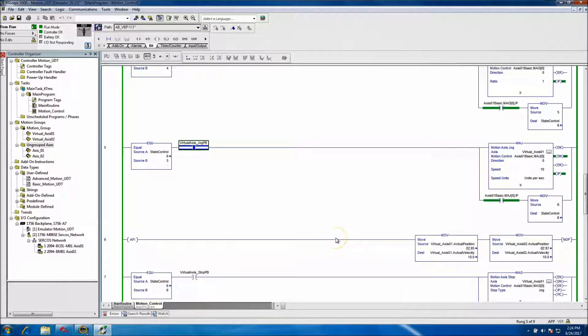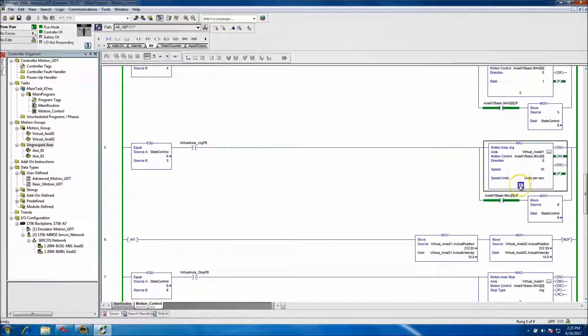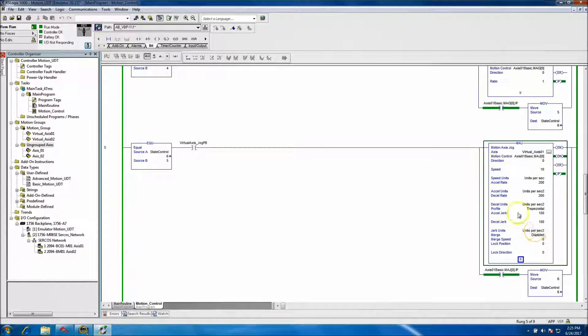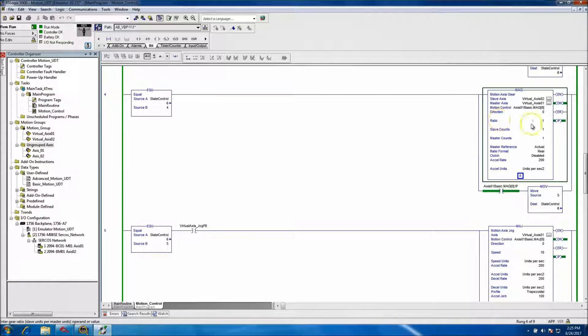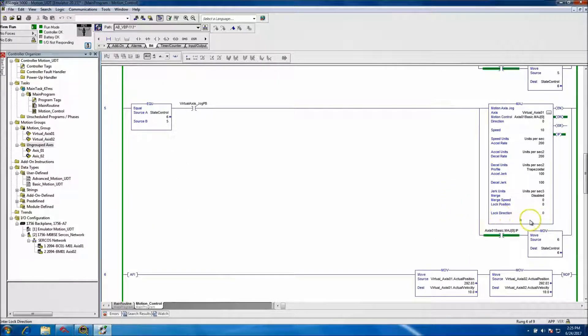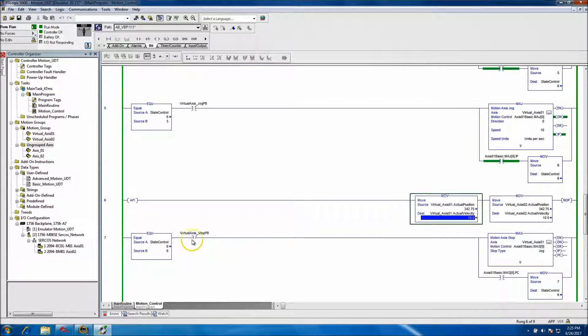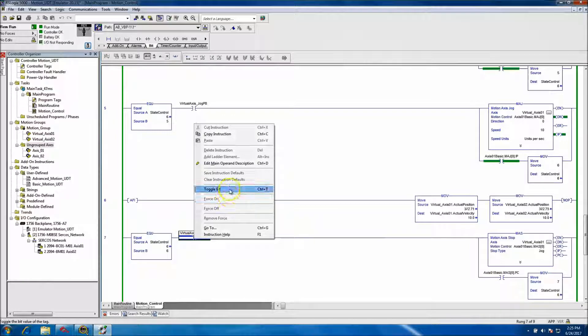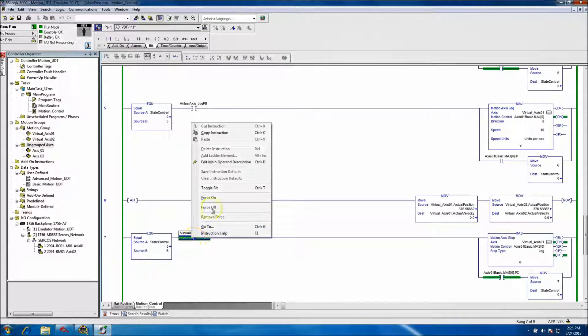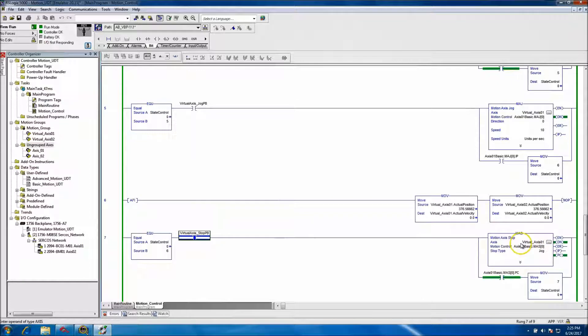Unlike a MAM which moves to a set position, here you can see both axes are actually moving together. I have a one-to-one gearing ratio, so whatever one is doing the other is doing. The velocity is 10. Now we can go down here and stop it. I'm only stopping Virtual Axis 1, but both axes stop because they are geared.